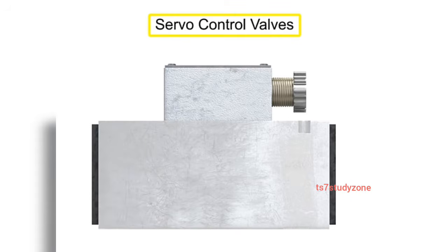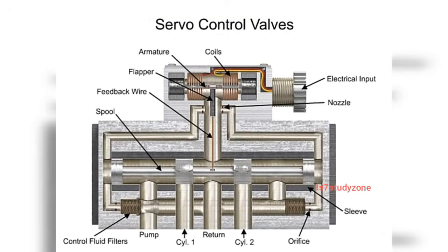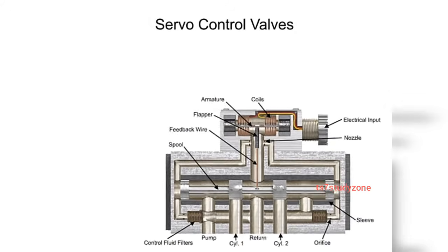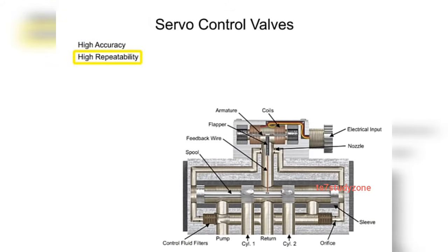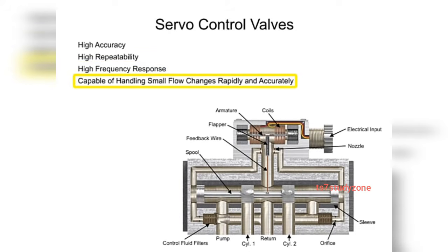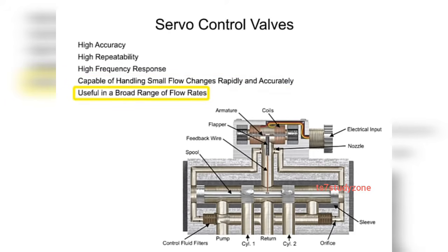Servo valve. First developed in the 1940s, the servo valves operate with very high accuracy, repeatability, and high-frequency response. Servo valves are highly responsive and capable of handling minuscule flow changes both rapidly and accurately over a broad range of flow rates, but at an extra cost.